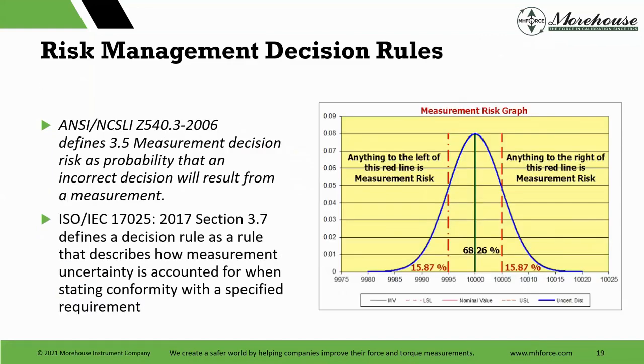And we look at this, here's two definitions. ANSI back to 2006: measurement decision risk is a probability that an incorrect decision will result from a measurement. It's an interesting definition. But then in 2017, they added how measurement uncertainty is accounted for when stating conformity with a specified requirement. Very distinct, very different definitions there if you look at it.